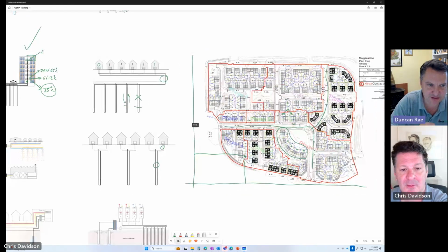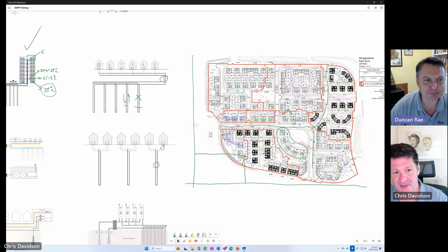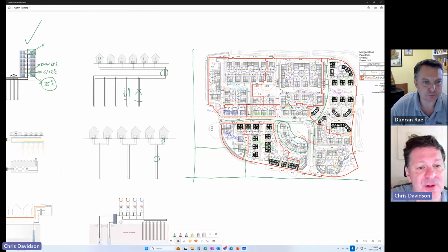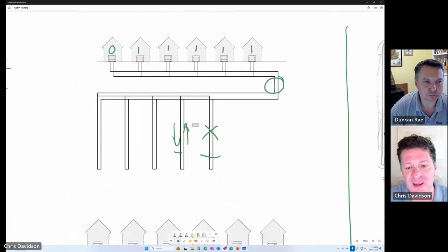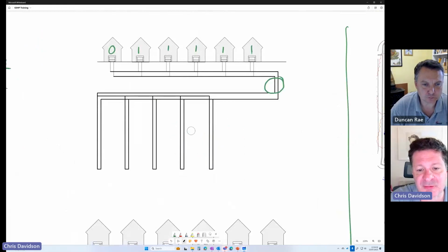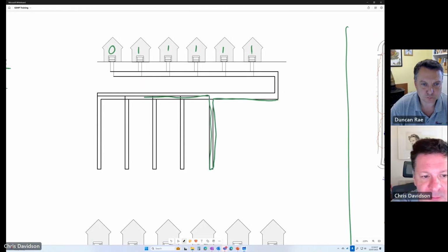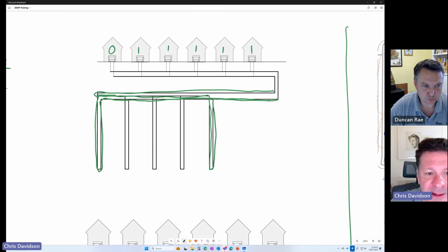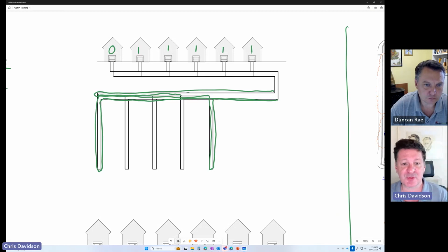Is the configuration in that diagram known as a reverse return? Yes, it is. A reverse return header, which you can see here, is a self-balancing header arrangement. If you walk a path down this nearest borehole and then back to the header again, and you walk the same path through the farthest borehole, then you can see that it's the same length of path. So that's the beauty of the reverse return header: it's self-balancing.